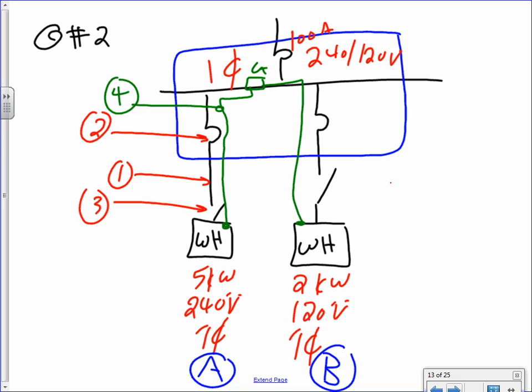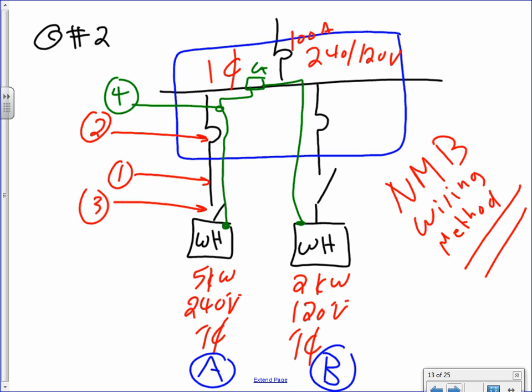So now add that I'm using NM-B wiring method. The wiring method, I'm still using NM-B. And I will bring to your attention, guys, both of them are single phase, but one is running at 120 and the other one is running at 240. Why did I pick these two voltages? Just to get you to understand how to work with two voltages on a single phase. Let me know when you guys are good.